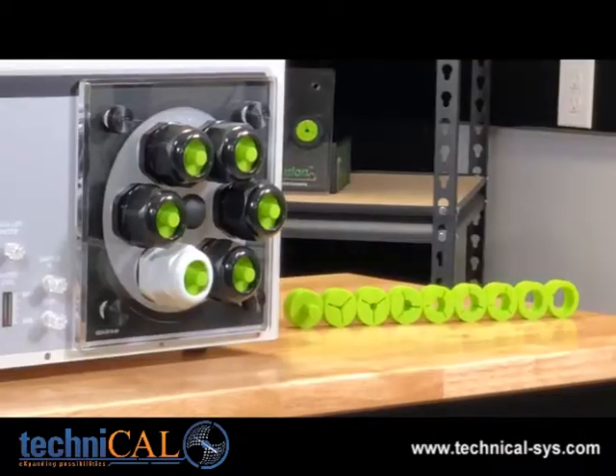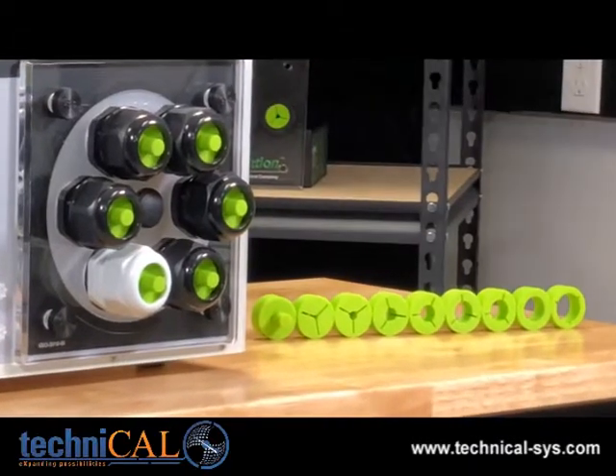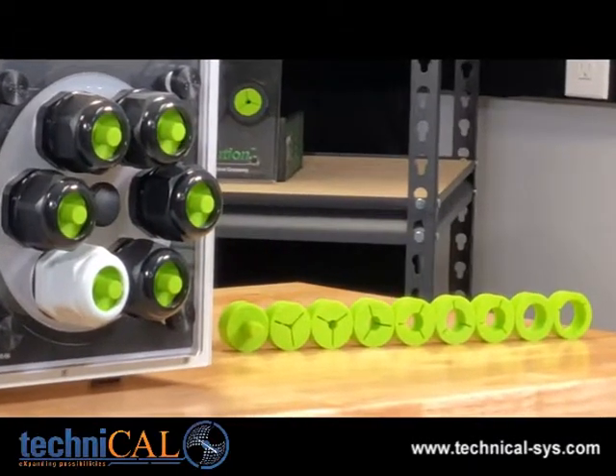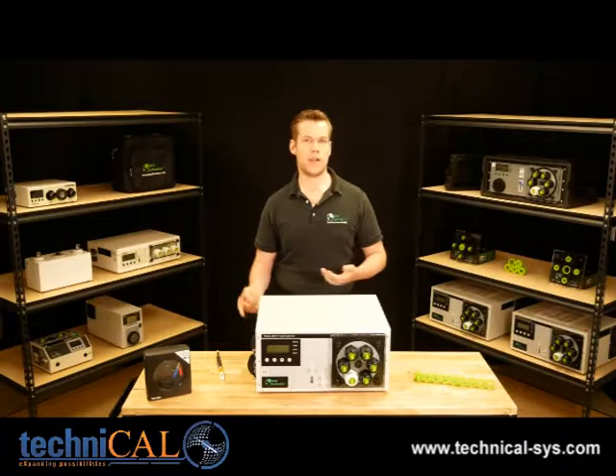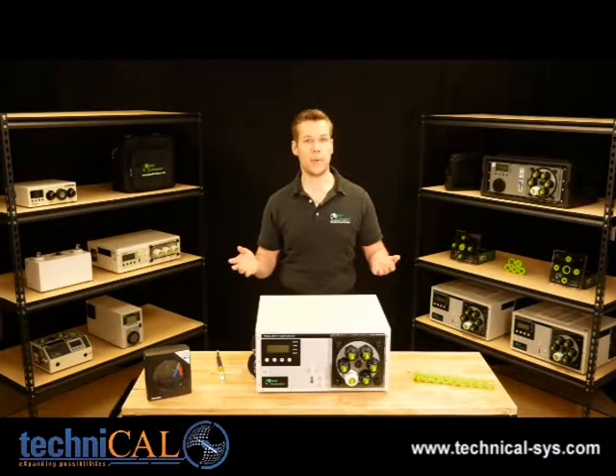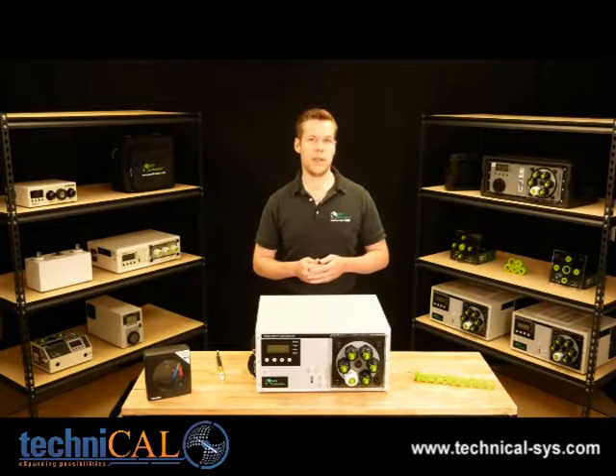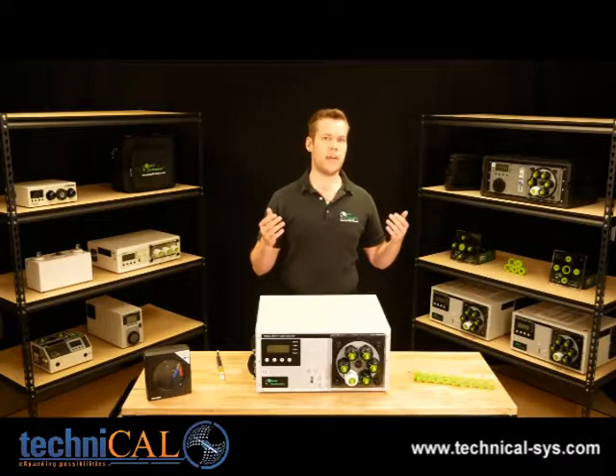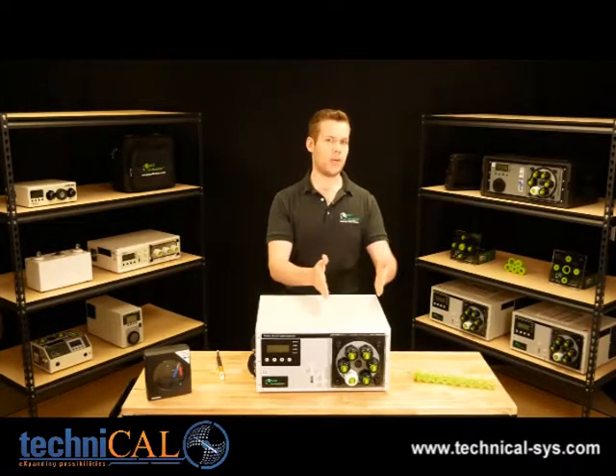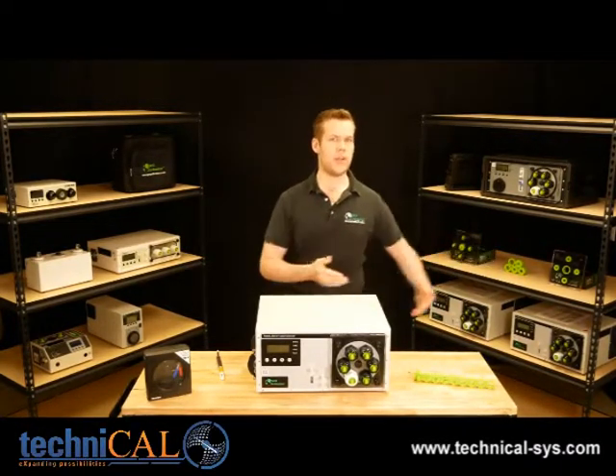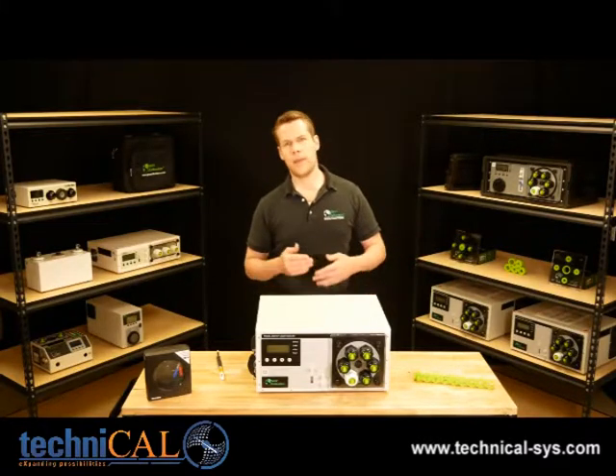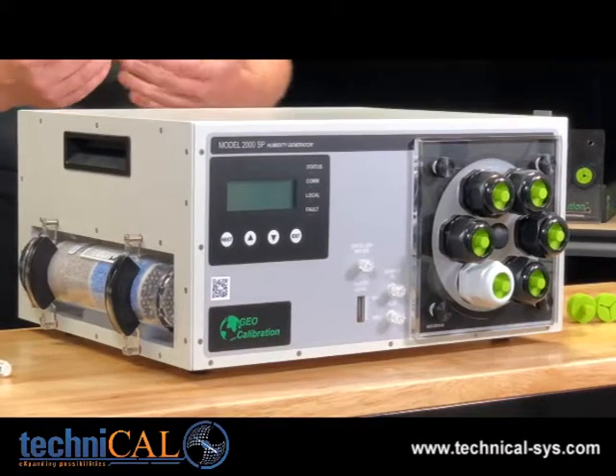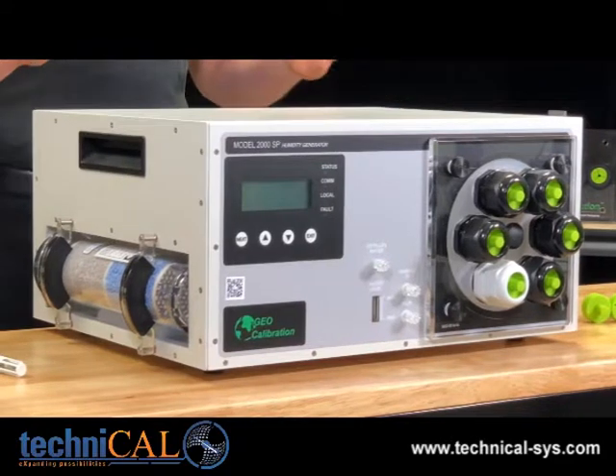This unit has 9 different bung size adapters and will calibrate every standard type of hygrometer. So your probes, data loggers, chart recorders, and even hair hygrometers will all work with this unit. The rule is, as long as you can fit the hygrometer inside either the chamber or the optional expansion chamber, you can calibrate it.